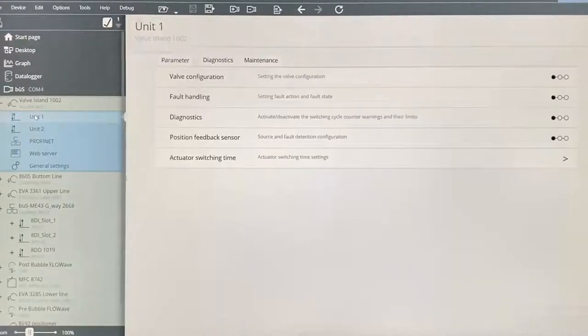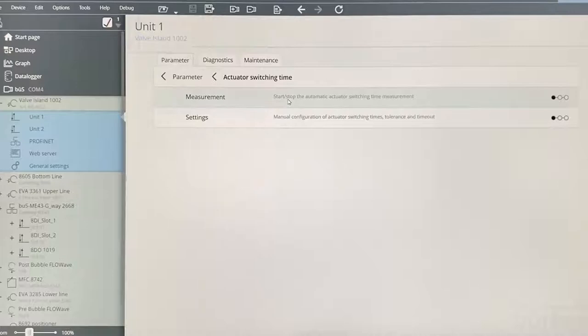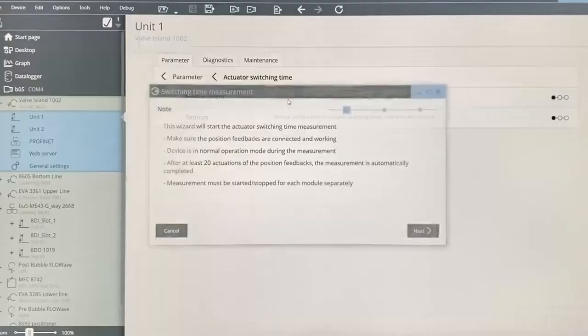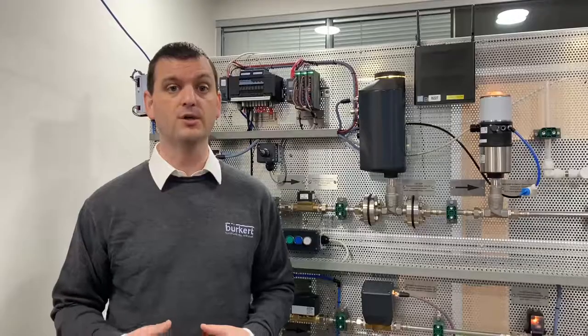This is found by selecting the valve island's module unit that is actuating the process valve. Next, we will select actuator switching time. We now have the option to run through the auto configuration using the measurement option. Alternatively, we can manually input the values through settings. For now, we will use the auto configuration. The wizard now informs us that it will monitor the next 20 actuations and log the average actuation time under the current conditions.